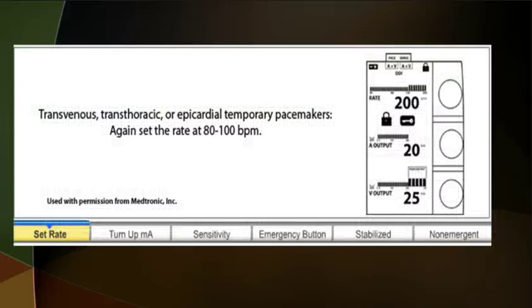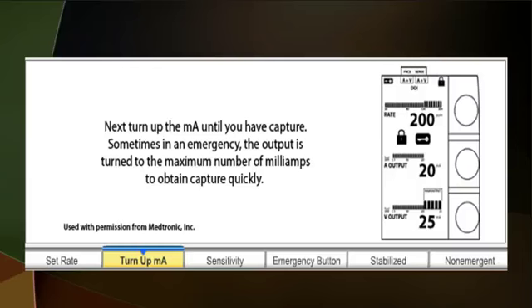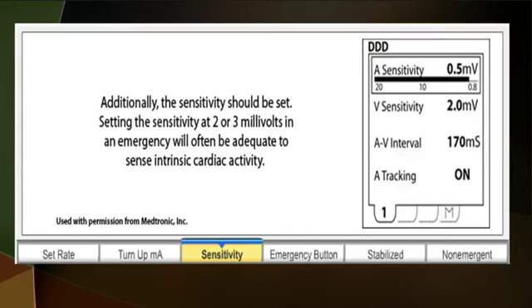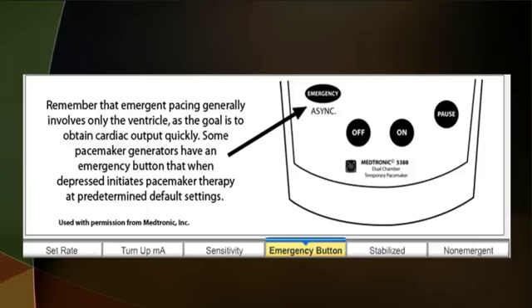Transvenous, transthoracic, and epicardial temporary pacemakers, set your rate to 80 to 100 beats per minute. Then you're going to turn your MAs up until you have capture. Sometimes in emergency, the output is turned to the maximum number of milliamps to obtain capture quickly. And the sensitivity should be set. Setting the sensitivity at 2 or 3 millivolts in an emergency will be adequate to sense intrinsic cardiac activity. There is actually on the pacemaker a button that says emergency. Emergency pacing involves only the ventricle, as the goal is to obtain cardiac output quickly.